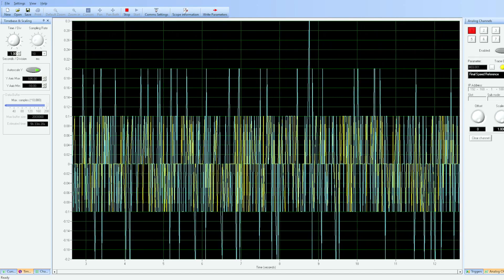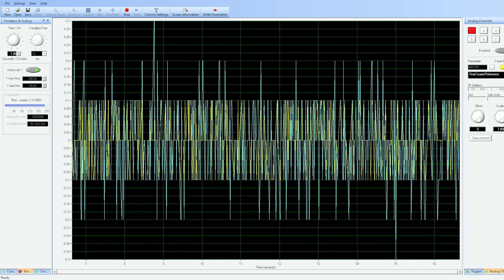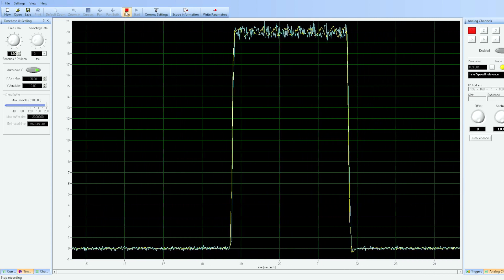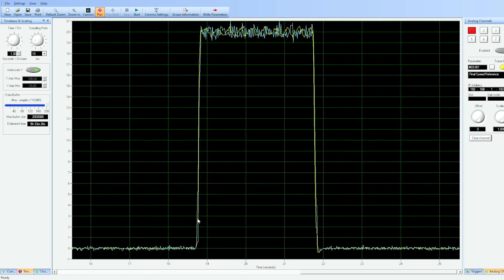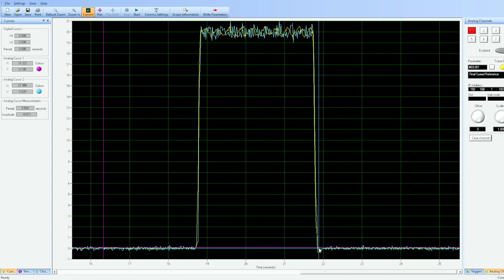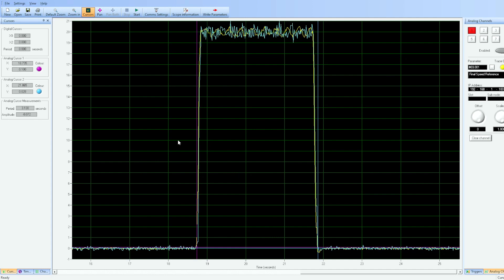Changing menu 34-07 from stop to position relative executes the profile. Looking at the CT Scope trace — using the cursors, the period between start and finish is approximately 3 seconds, confirming the move completed in the target time. The calculations were correct for the trapezoidal move.